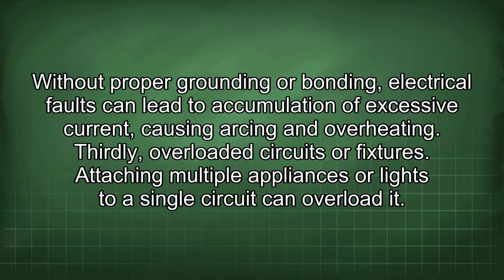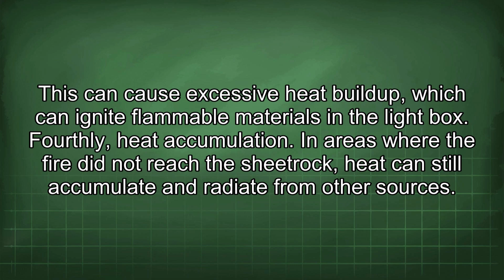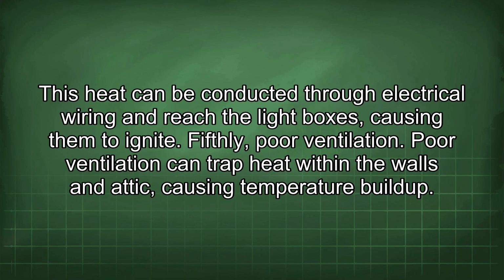Thirdly, overloaded circuits or fixtures. Attaching multiple appliances or lights to a single circuit can overload it. This can cause excessive heat buildup, which can ignite flammable materials in the light box. Fourthly, heat accumulation. In areas where the fire did not reach the sheetrock, heat can still accumulate and radiate from other sources. This heat can be conducted through electrical wiring and reach the light boxes, causing them to ignite.